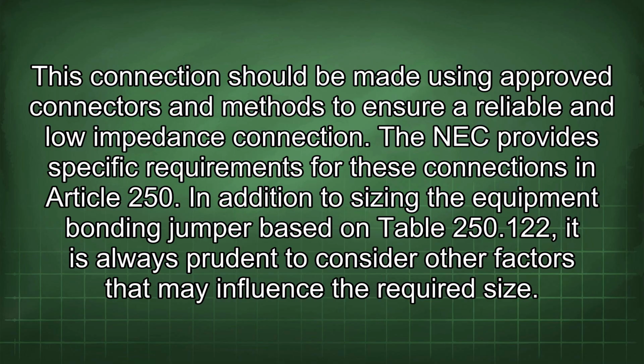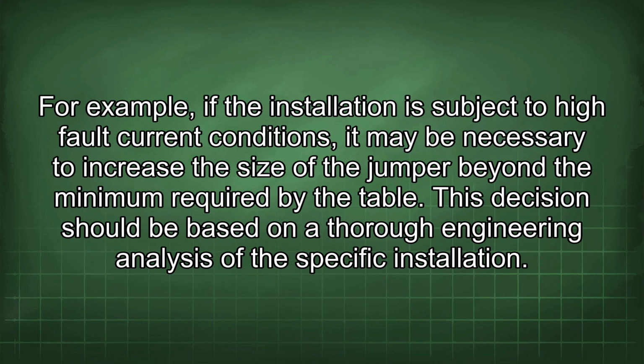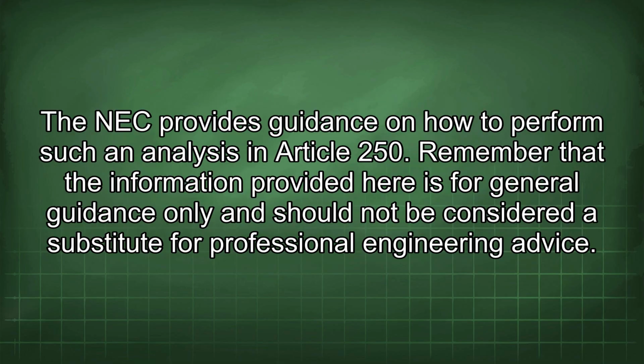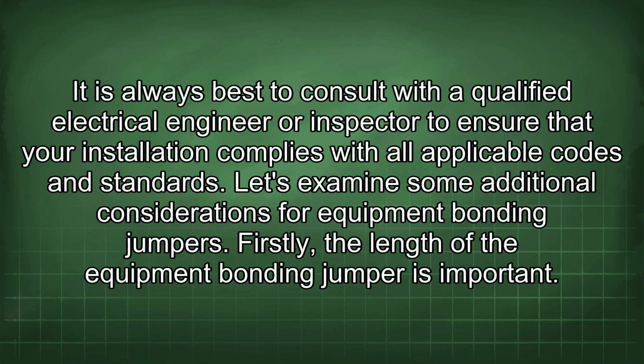In addition to sizing the equipment bonding jumper based on Table 250.122, it is always prudent to consider other factors that may influence the required size. For example, if the installation is subject to high fault current conditions, it may be necessary to increase the size of the jumper beyond the minimum required by the table. This decision should be based on a thorough engineering analysis of the specific installation. The NEC provides guidance on how to perform such an analysis in Article 250. Remember that the information provided here is for general guidance only and should not be considered a substitute for professional engineering advice. It is always best to consult with a qualified electrical engineer or inspector to ensure that your installation complies with all applicable codes and standards.